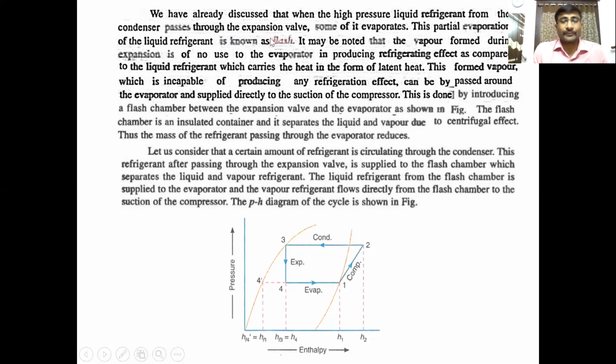Because flash cannot absorb the heat. It is already in the vapor state. Only the liquid particles will absorb the heat in the evaporator. So the vapor formed during the expansion is of no use to the evaporator in producing the refrigeration effect, as compared to liquid refrigerant, which carries the heat in the form of latent heat. So liquid only absorbs the latent heat. The flash does not absorb the heat. This formed vapor is incapable of producing any refrigeration effect.